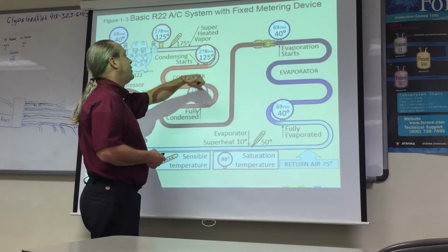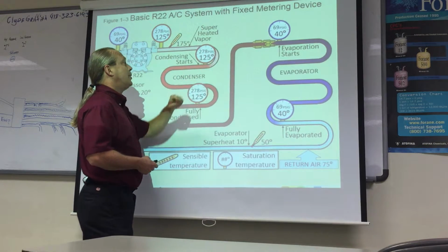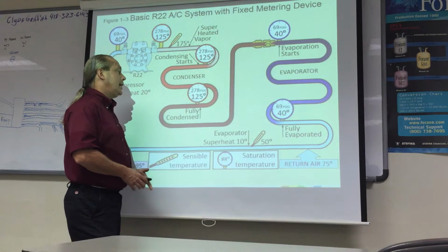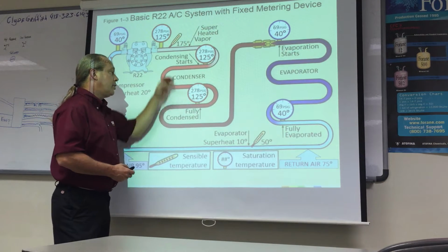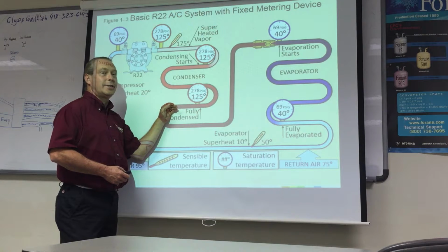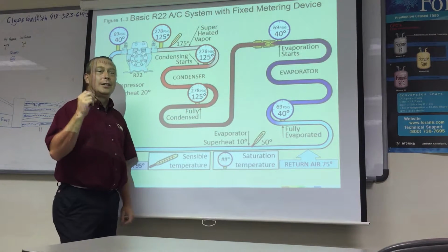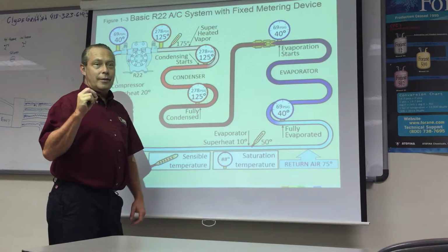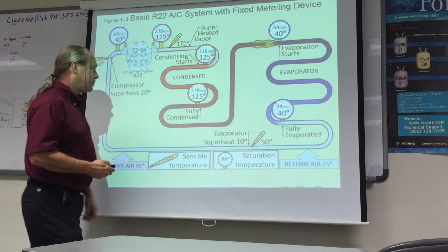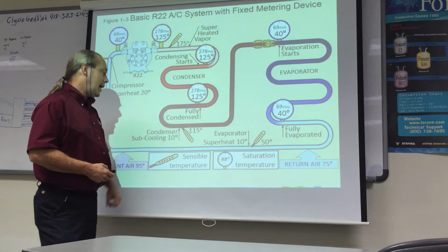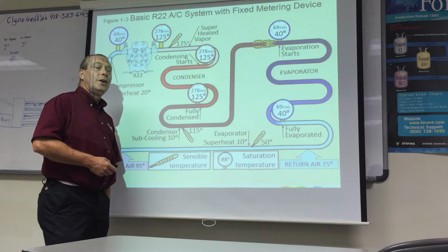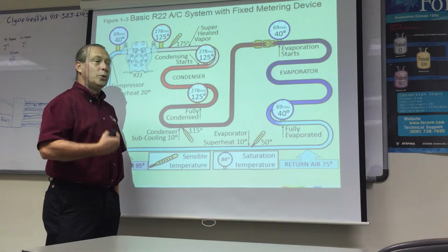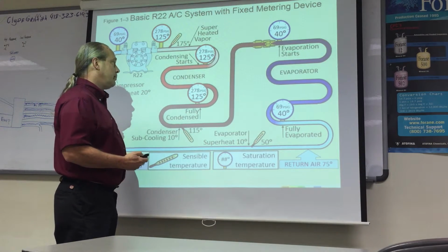By the time it starts showing red, we've exhausted all of our superheat and we are beginning to condense once more. There's no temperature change through the condenser until we have alleviated ourselves of the last bubble of gas refrigerant. And now we can subcool because we have made that change of state, and now we can actually cool down the liquid refrigerant.